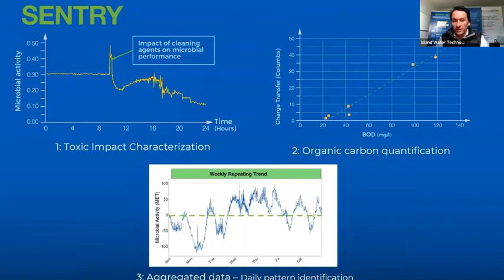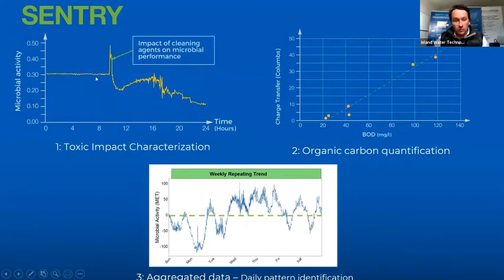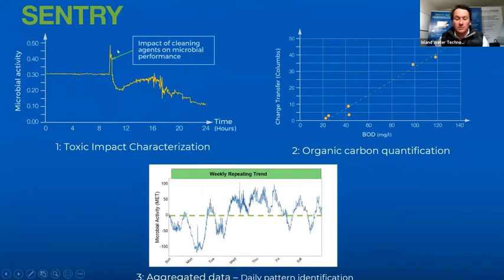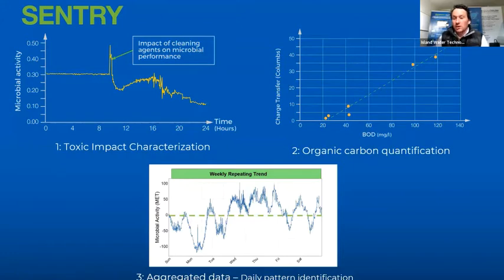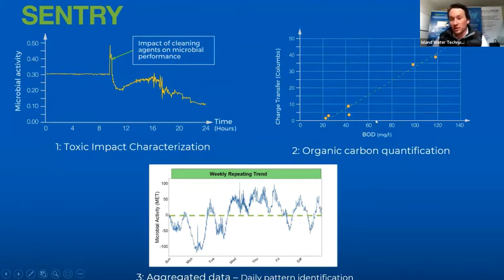There are three types of data we provide. First, using the platform in a primary clarifier to identify biological imbalance — perhaps a significant dilution event, infiltration, or something acutely toxic in your wastewater stream. You can see very steady-state biofilm activity, then something comes in and causes a significant drop-off in microbial activity. Second, we measure the rate at which the biofilm oxidizes bioavailable carbon. If we provide the biofilm more carbon, you get a higher signal; less carbon gives a lower signal. So we can provide not just an estimate of how much BOD is available, but how much BOD is being consumed by the biology in real time.